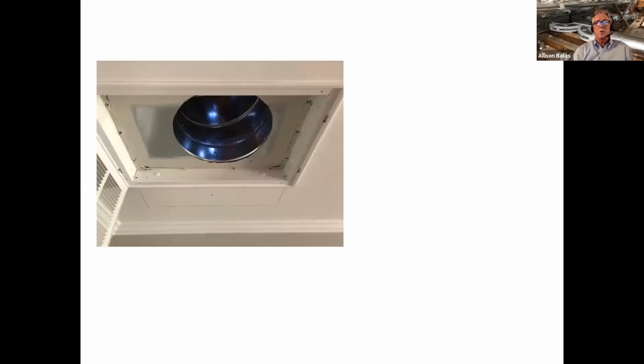So another thing. Here's what I was talking about, what I didn't like. When they first installed the system, I didn't pay attention to this part, but my 2-inch filter goes in this gap up here, which meant this piece of sheet metal was right on the back side of my filter. And the duct goes in, and so a lot of the air was going straight through the middle of the filter and not as much through this part.